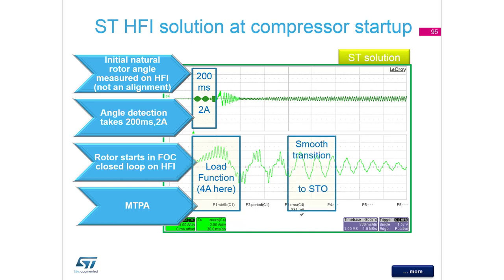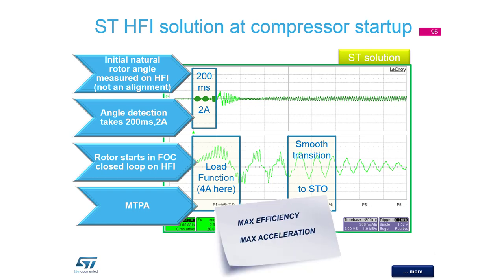With HFI, the benefit is maximum efficiency because we apply only the necessary current, and fast acceleration because we know the rotor position precisely. That is the goal of the sensorless zero speed algorithm.